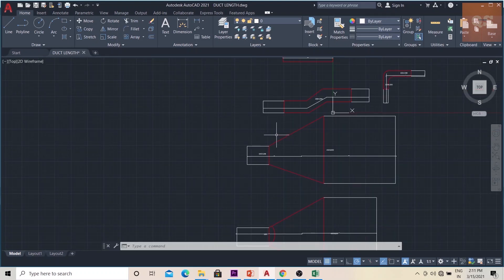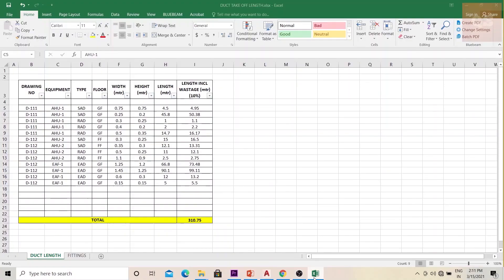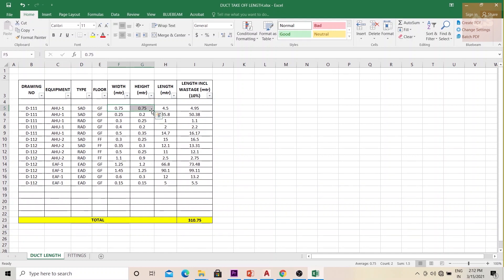All these can be recorded in an Excel sheet. I've made a sheet where you mention which drawing you're taking off the quantity from, which AHU or equipment you are taking the length from. It is always better to calculate the length of ducts from each equipment to avoid confusion. From AHU1, you mention the type of duct — supply air, return air, or extract air — the floor, the dimensions (width and height), and the calculated length. You can add a wastage of 5 to 10%. This sheet is not including the fittings; if fittings need to be separately counted, only the rectangular piece is recorded here.